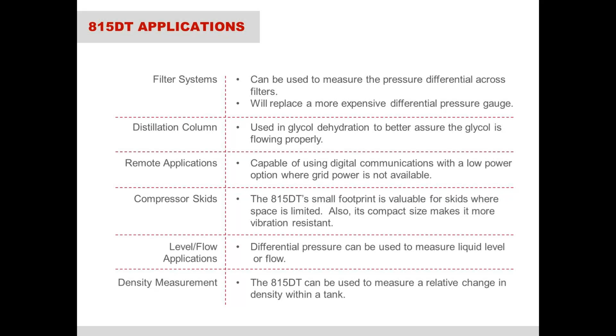Distillation columns, remote applications, compressor skids, but also the 815DT can be used to measure level by taking the pressure at the bottom of the tank and the pressure at the top. This gives you a level output of a tank that is sealed. Remember, the submersible level transmitter is used for vented tanks that are exposed to atmospheric pressure, whereas the differential pressure transmitter is used for tanks that are sealed, because you need reference to the top pressure of the tank.